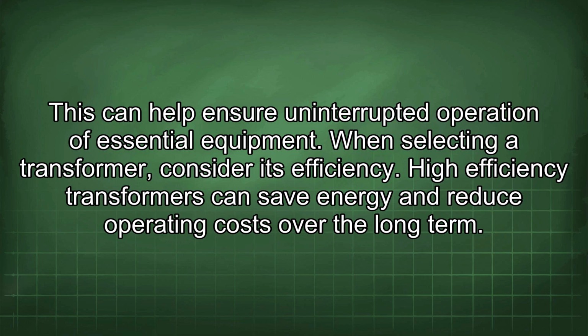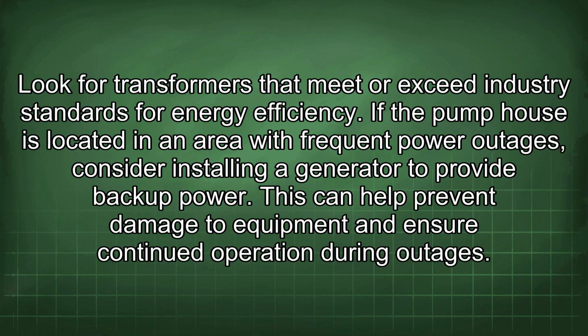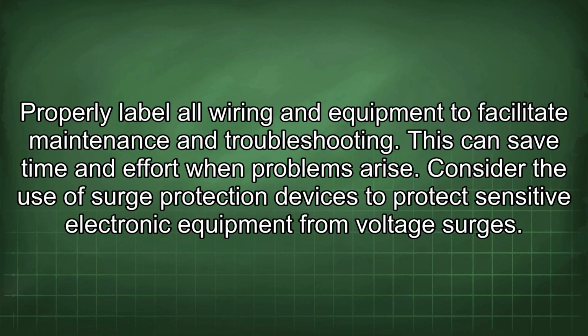When selecting a transformer, consider its efficiency. High-efficiency transformers can save energy and reduce operating costs over the long term. Look for transformers that meet or exceed industry standards for energy efficiency. If the pump house is located in an area with frequent power outages, consider installing a generator to provide backup power. This can help prevent damage to equipment and ensure continued operation during outages. Properly label all wiring and equipment to facilitate maintenance and troubleshooting. This can save time and effort when problems arise.